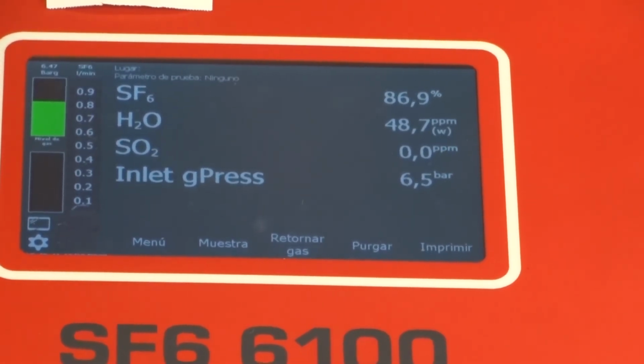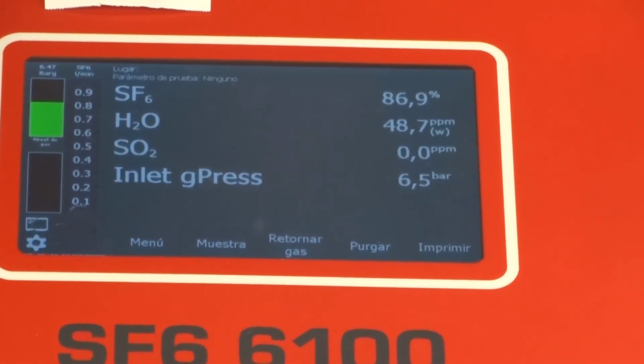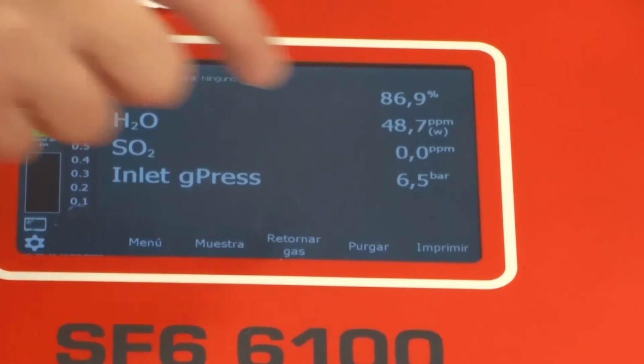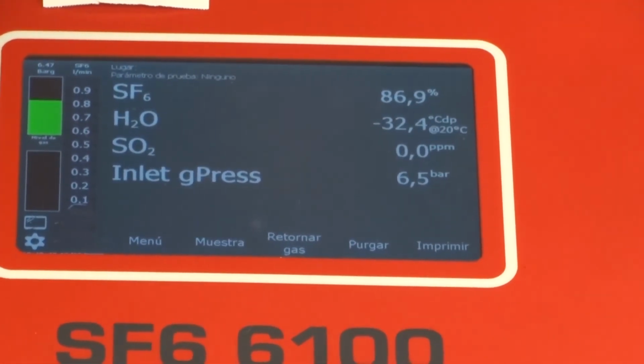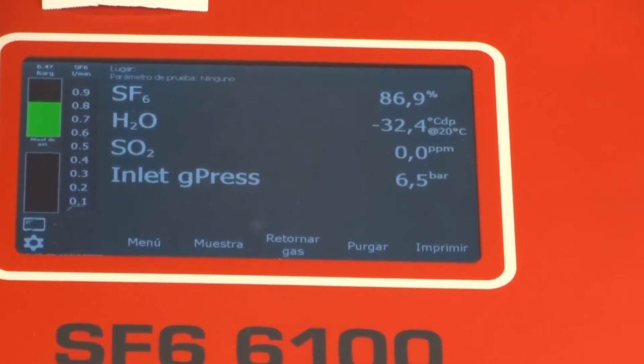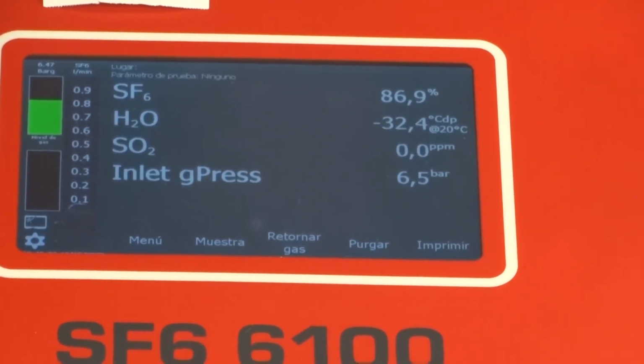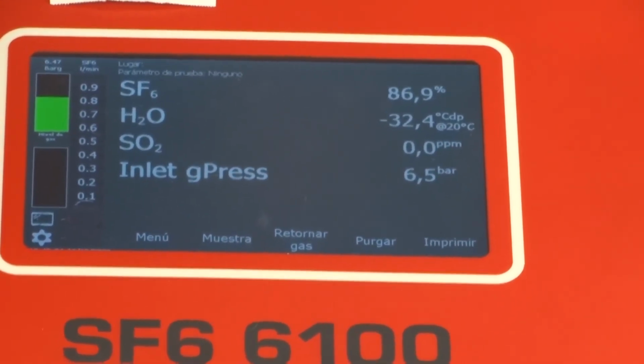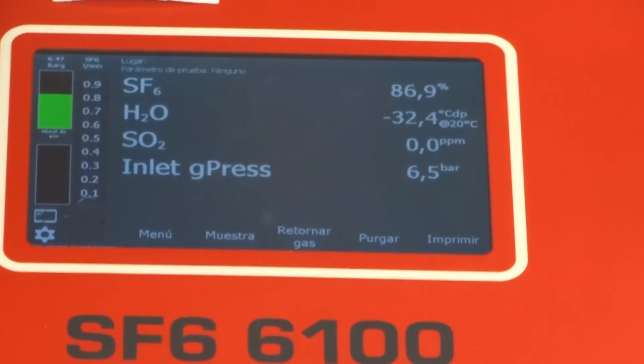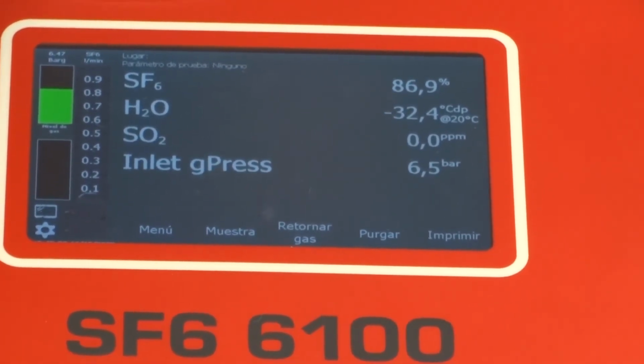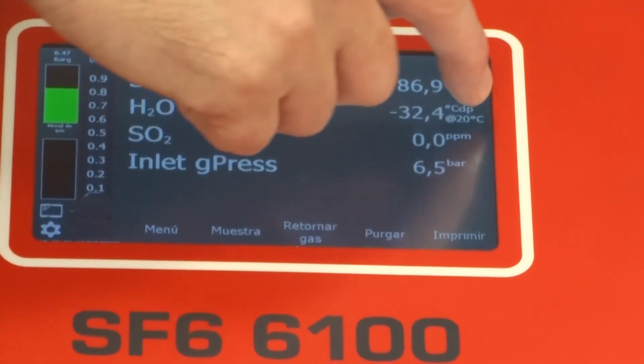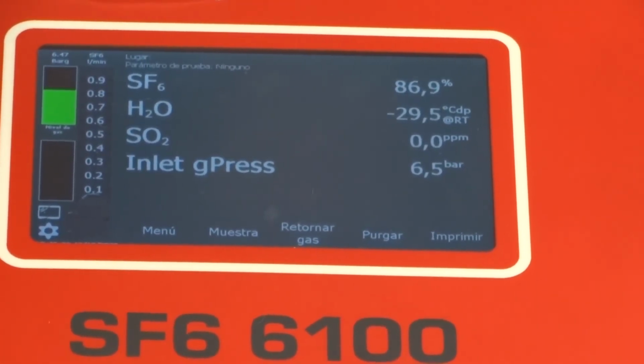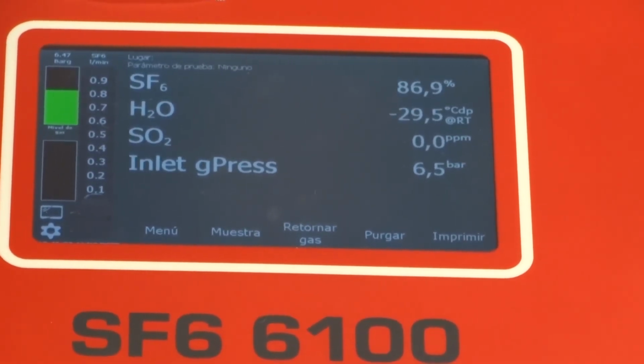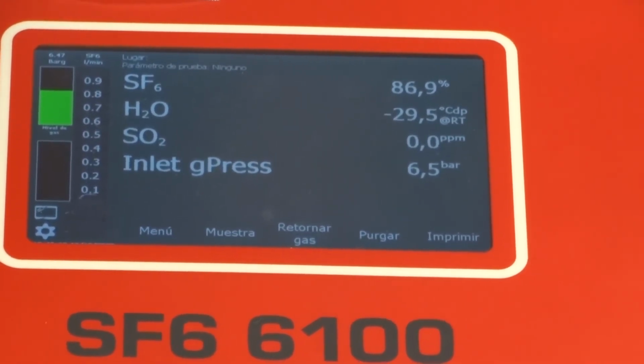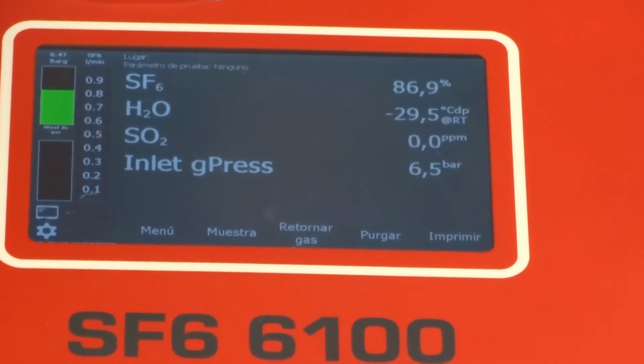Or you can have ppm by weight of water, which is 48.7 ppmw. And the dew point is either harmonized to a reference point of 20 degrees Celsius, which is this result of minus 32.4, or you can select it to room temperature, which is the gas compartment temperature. So this is minus 29.5 at room temperature CDP.